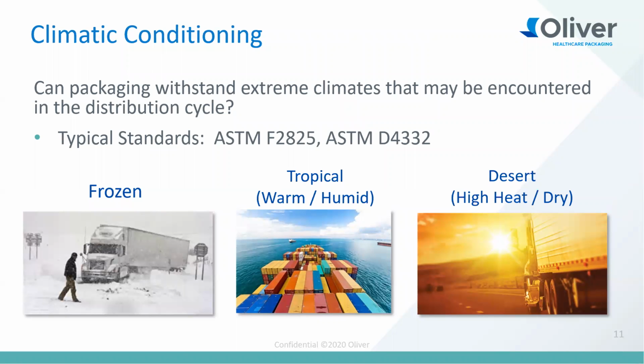Yeah, thanks, Jeremy. So, as we said, once you've defined the plan and you have your worst case selected, you have your samples built, you have your sterilization completed, the first step is climate conditioning. And you might ask, well, why do I have to do climate conditioning? It sounds a bit extreme, but obviously the environment that the product is manufactured and converted in may not always necessarily be the same as where it's going to end up. So you need to ensure that no matter what condition or environment it is in, that it's going to pass. So you need to subject the product and the packaging to various different conditions, whether it be frozen, warm and humid, or high heat and dry as well.